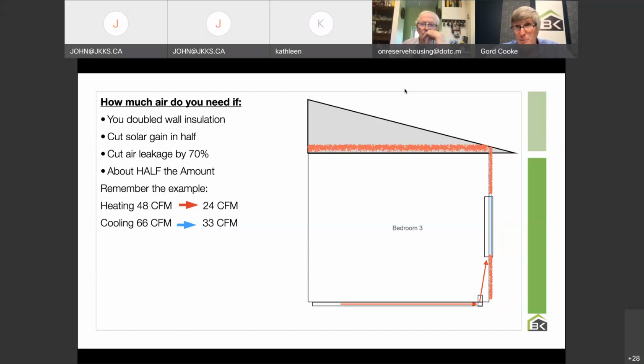And then I can determine from there, if I'm using a forced air heating system, exactly how much heat and how much air I need to each individual room. Or in the case of electric heat, how big an electric baseboard heater do I need in that particular room? So it means we can stop oversizing systems when, typically, people say, well, I'll just put in a 1 kilowatt baseboard heater, 1 kilowatt, 1 kilowatt, 1 kilowatt, and all of a sudden you need a huge amperage service size, whereas you found, well, this bedroom only needs 250 watts and this bedroom only needs 500 watts. Now I can reduce my service size and obviously bills go down and so on.